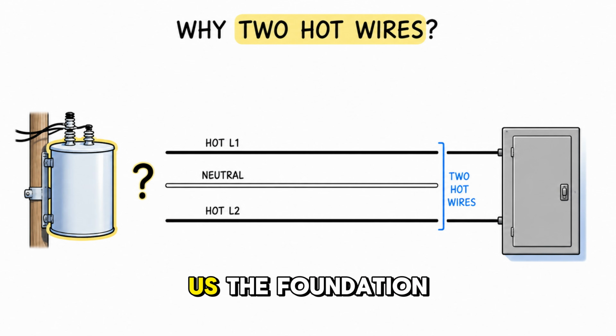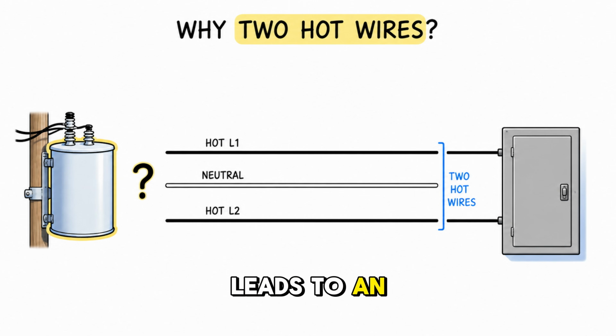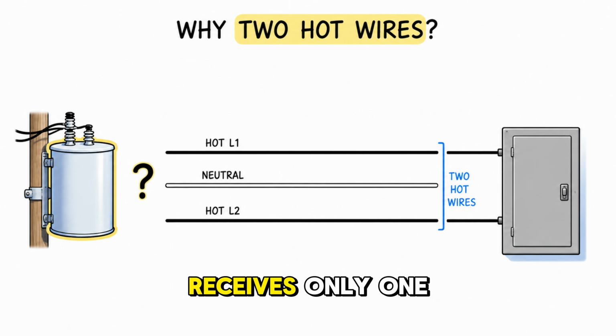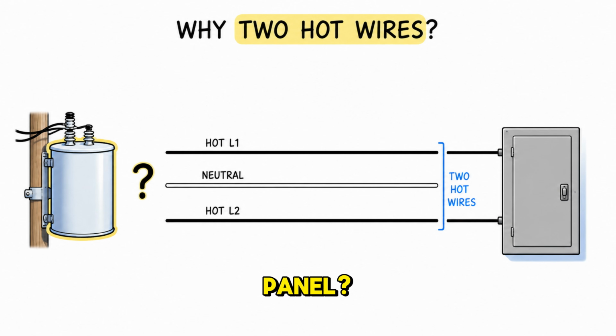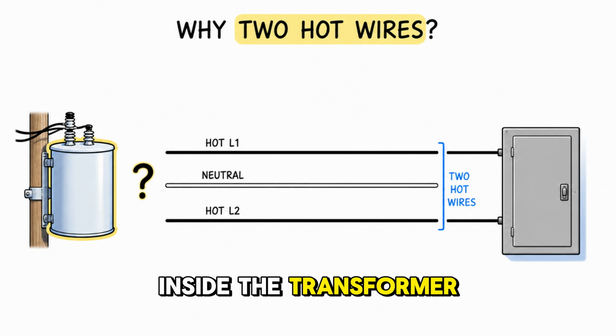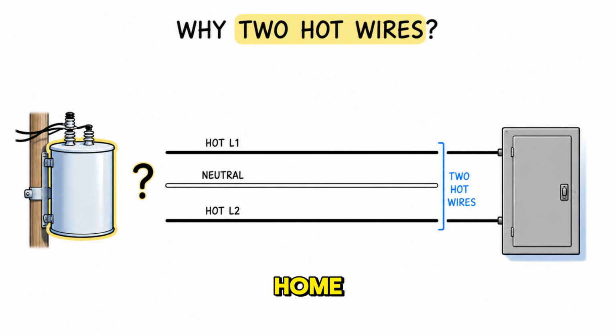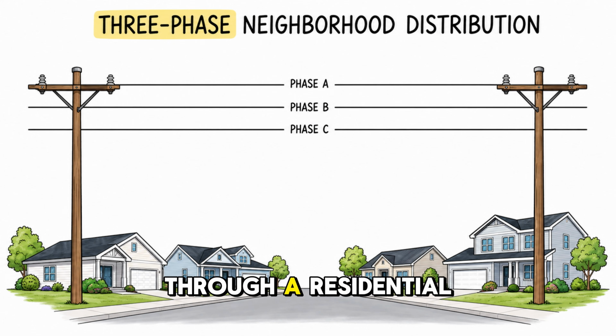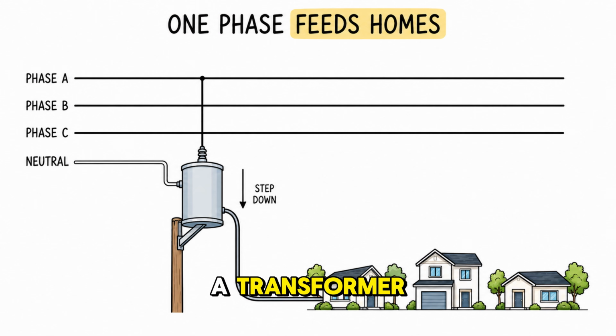That definition gives us the foundation, but it also leads to an important question. If a home receives only one phase, why do 2 hot wires normally enter its panel? The answer is waiting inside the transformer that supplies the home. The distribution lines passing through a residential area may belong to a larger 3-phase network. A transformer supplying nearby homes often connects to one phase of that network and reduces the distribution voltage to a level that household equipment can use.